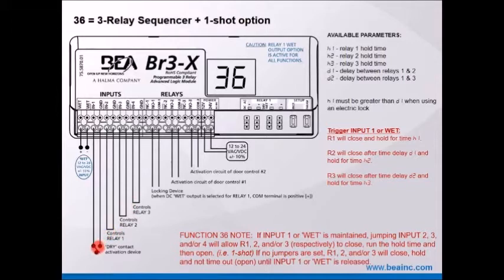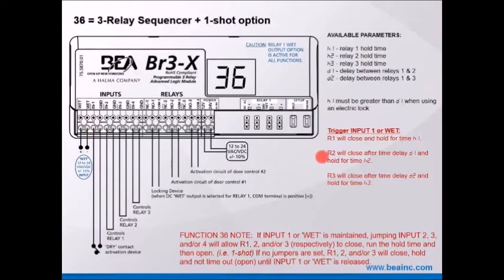In the past, if you make and hold the input, all outputs will change and hold — the hold timer will freeze and not start counting down until the input releases. Not the case when you put a jumper on input two, three, or four. Relay two will close after time delay D1 and hold for H2. Relay three will close after D2 delay and hold for H3.